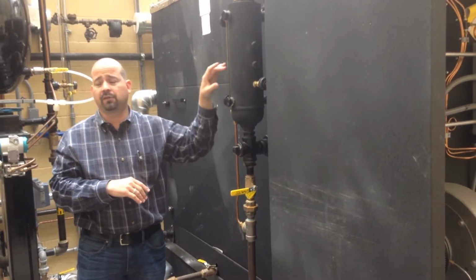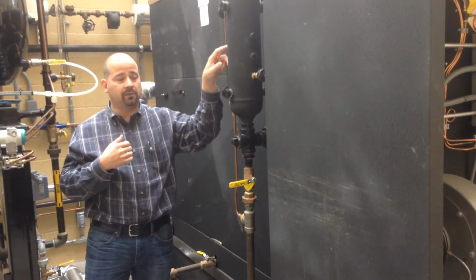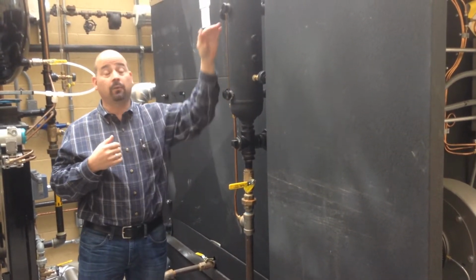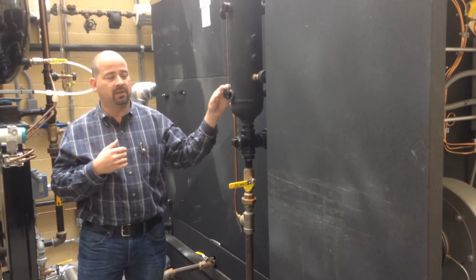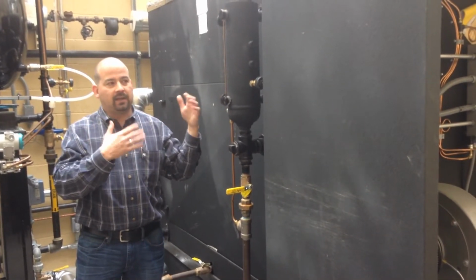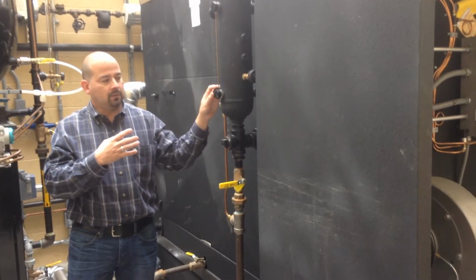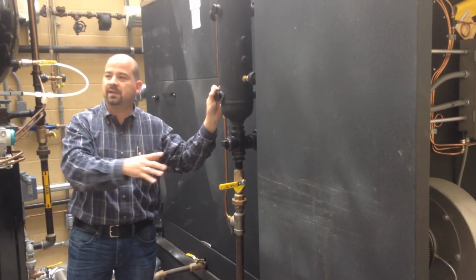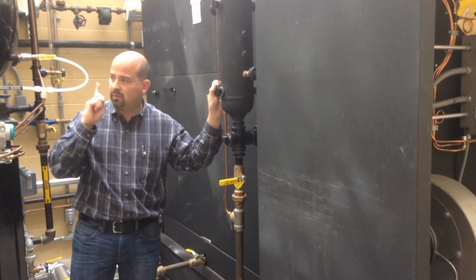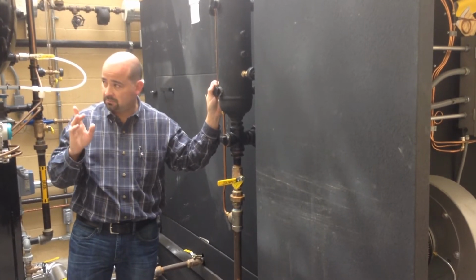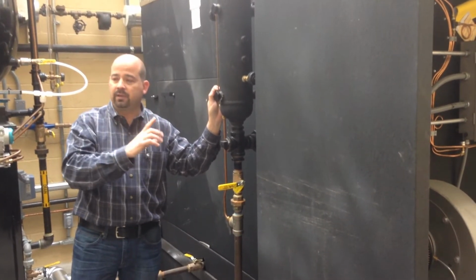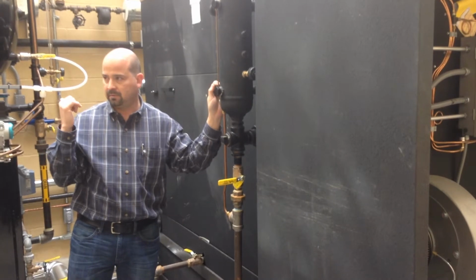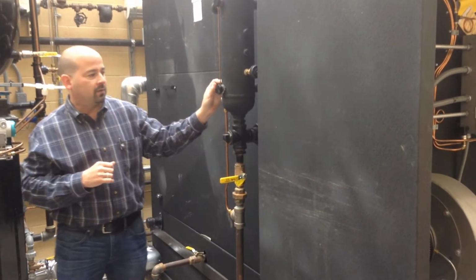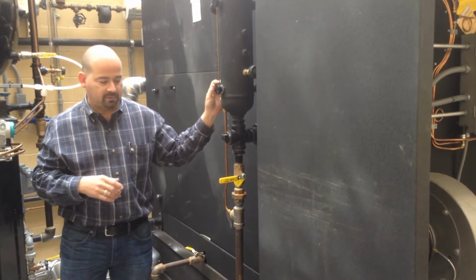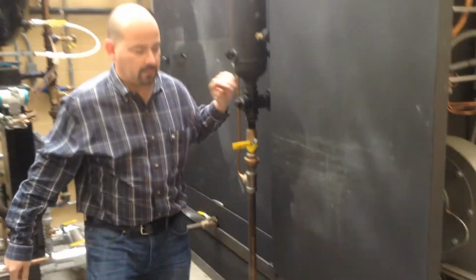And then you have start-stop probes for your pump in here as well. And then you have a high water probe. So you have a lot of safety functionality here, and all of the safeties on this boiler are tied into one relay. So if anything goes wrong, that one relay will close the set of contacts and go to the delta feed. Okay. And it'll sound an audible alarm too. So let's go ahead and go over the side here.